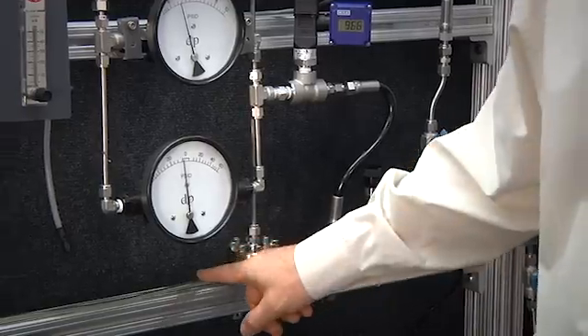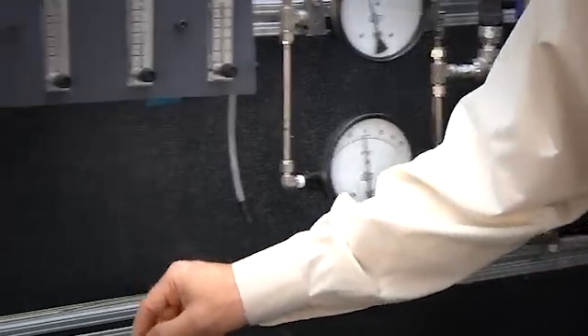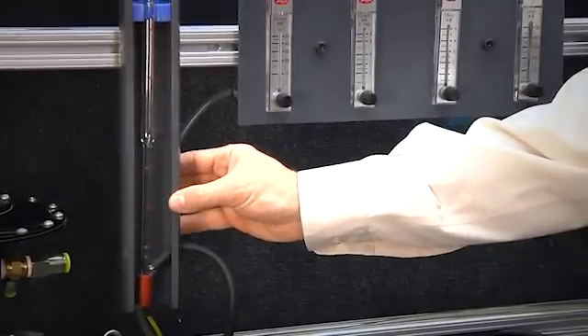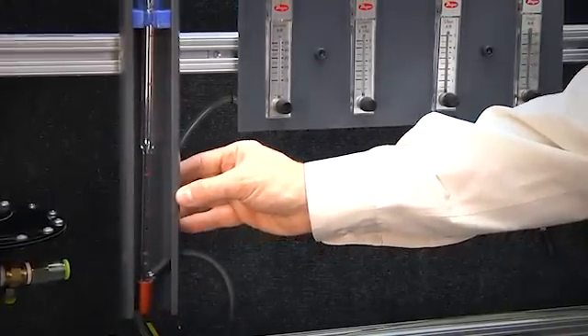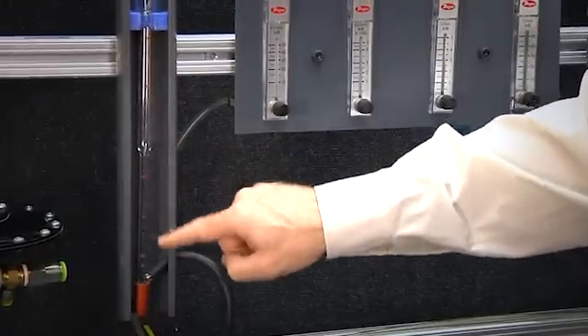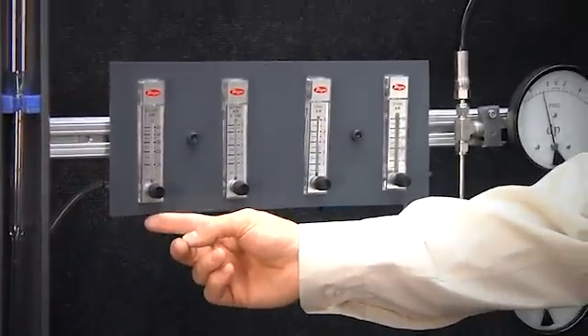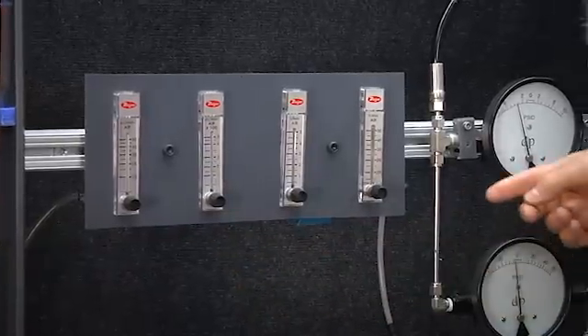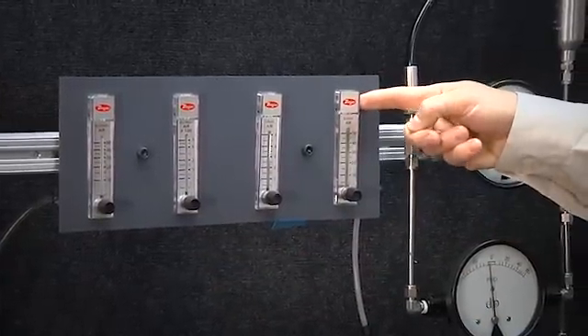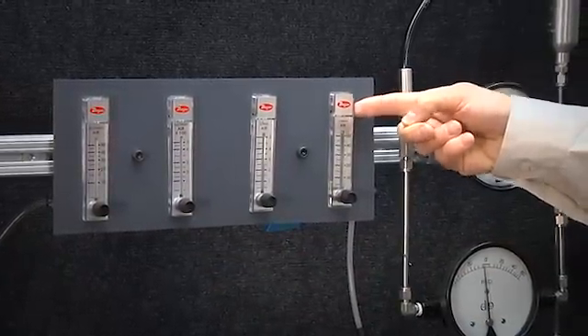For the flow rate coming out of the regulator we are going to first measure with a bubble meter to do the micro flows in the range of 1 milliliter per minute. At higher flow rates we are going to pass through 4 decades of Dwyer rotameters all the way up to the largest being 50,000 cc's per minute or 50 liters per minute.